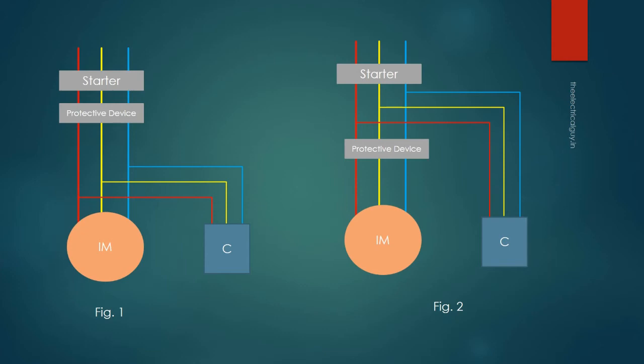It will self-excite with the reactive energy drawn from the capacitor bank and may turn into a synchronous generator. Hence, to avoid this, it is strongly recommended to use a separate switching device for the capacitor bank as shown in figure 3.